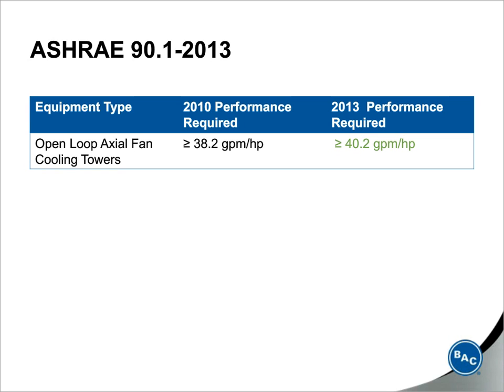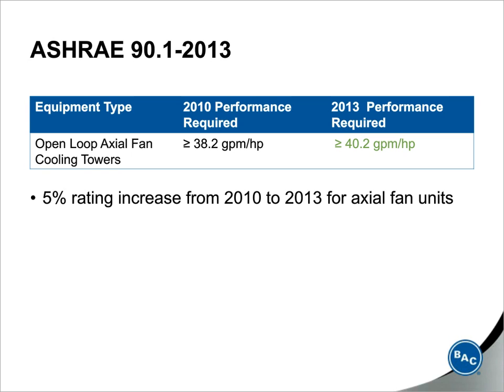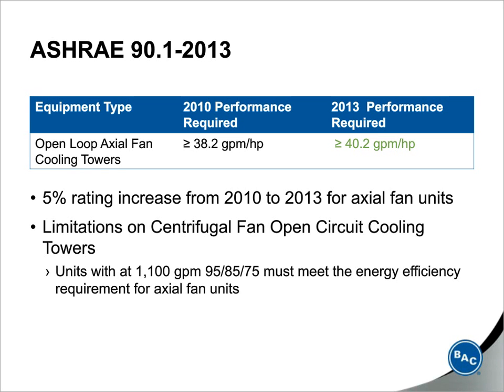It's been very, very widely adopted. From 2010 to 2013, the minimum energy requirements for axial fan units increased from 38.2 GPM per horsepower to 40.2 GPM per horsepower. And this represents about a 5% increase in energy requirements since the 2010 code release. Now, centrifugal fan cooling towers, which use about twice the energy of axial fan towers, haven't increased in minimum efficiency requirements. However, there are now limitations in place that require the same rating as axial fan units for centrifugal fan units above a certain tonnage.